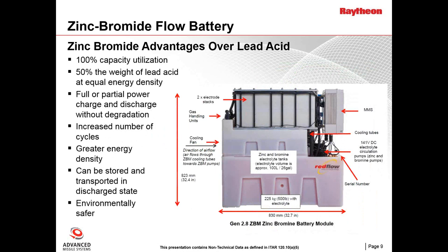The zinc-bromine batteries from Redflow have advantages over lead-acid: 100% capacity utilization, 50% of the weight of lead-acid at equal energy density, full or partial power capability, increased number of cycles — which they continue to improve with the technology — greater energy density, ability to be stored and transported in the discharge state, and overall a more environmentally safe battery.